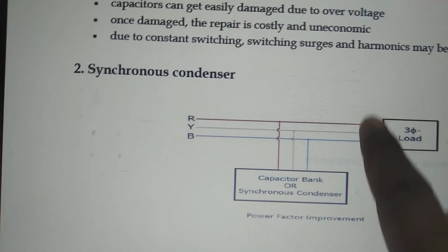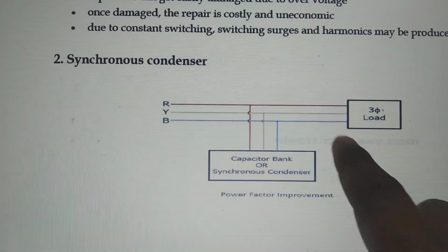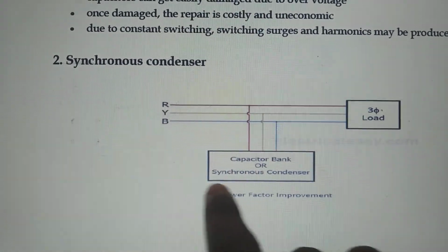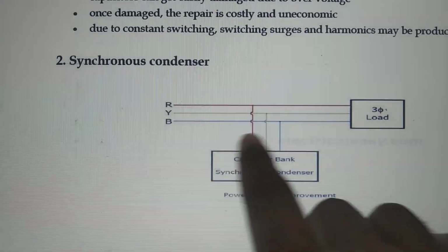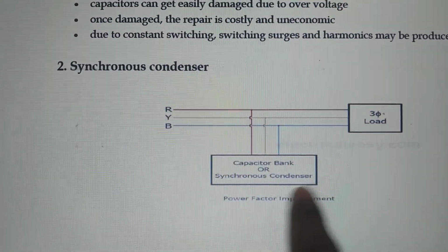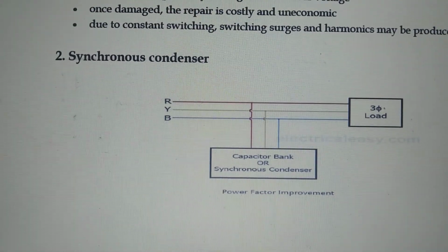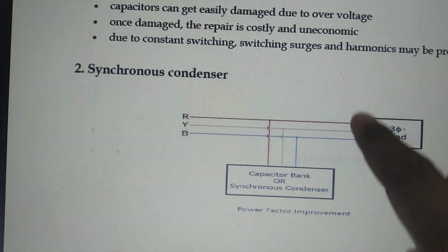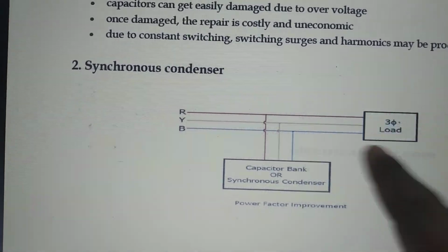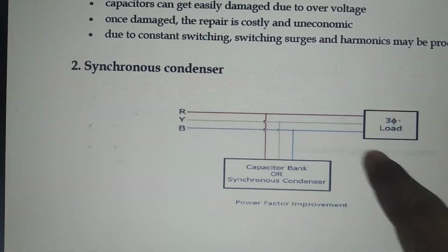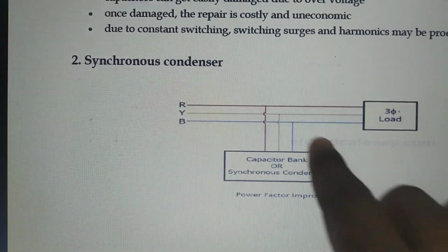We can say this is a three-phase inductive load, and we are connecting one synchronous condenser in parallel to the system, and this synchronous condenser will produce reactive power which is pumped into the system. Basically, this inductive load absorbs the reactive power of the system, and this reactive power is compensated by the reactive power produced by the synchronous condenser.